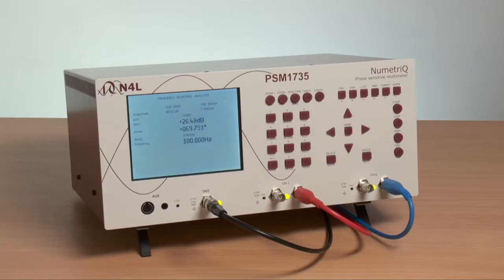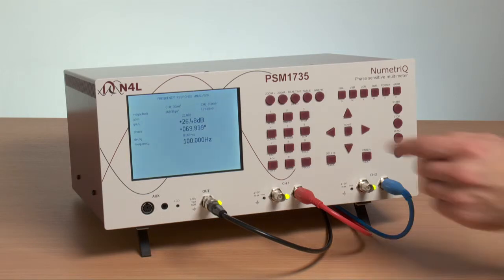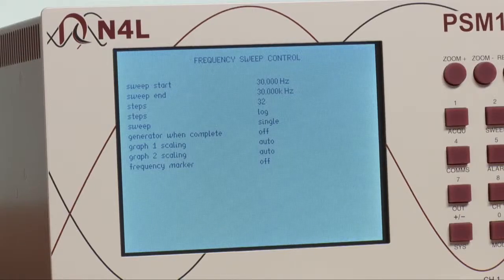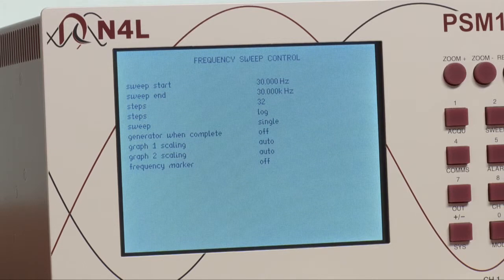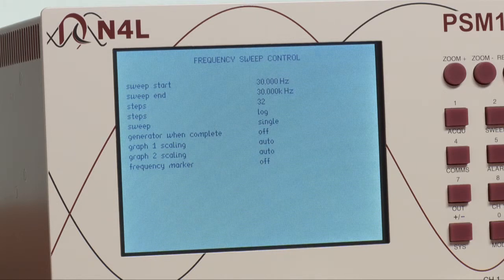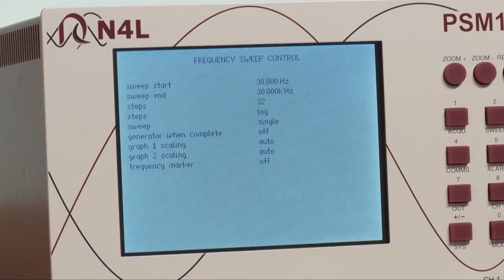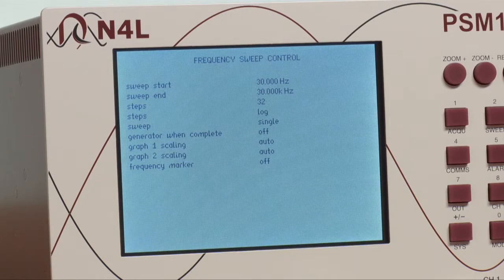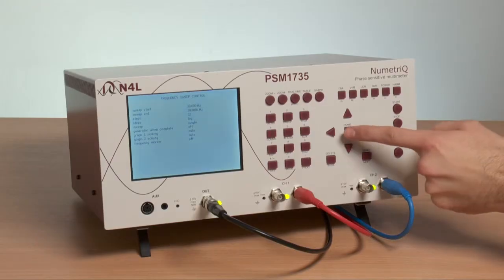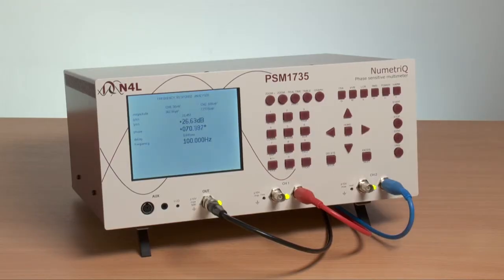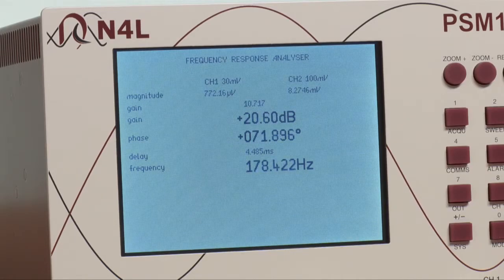Normally, however, loop response measurements are made over a frequency sweep. So we will go into a sweep menu, where we have preset a frequency range of 30 Hz to 30 kHz. This range can be set to any frequency range from 10 microhertz to 1 MHz in the PSM 1700, or 10 microhertz to 35 MHz in the PSM 1735. We have selected 32 steps for the sweep, log plot, and a single sweep. If we now come back to the measurement mode and press start, you can see that the frequency is stepping up and the values of gain and phase are changing.